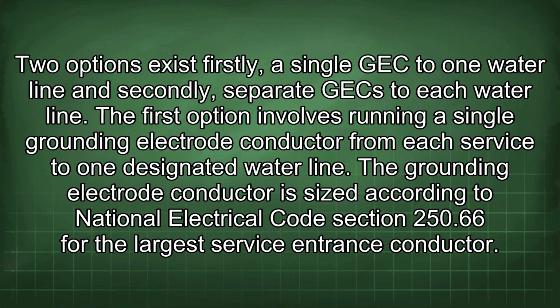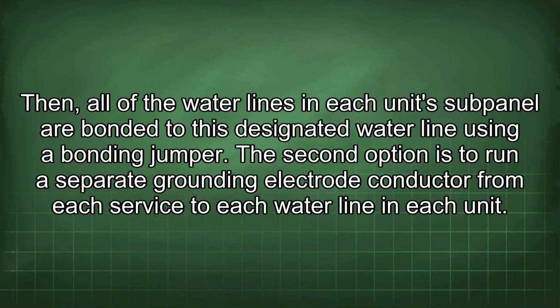The first option involves running a single grounding electrode conductor from each service to one designated water line. The grounding electrode conductor is sized according to National Electrical Code Section 250.66 for the largest service entrance conductor.